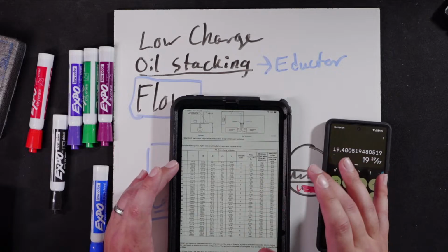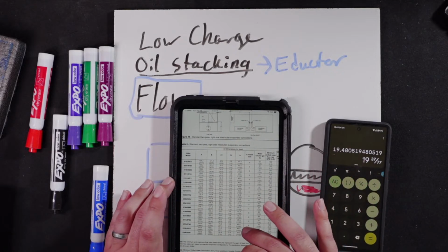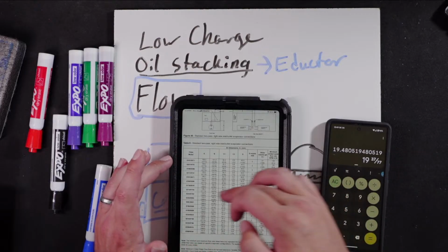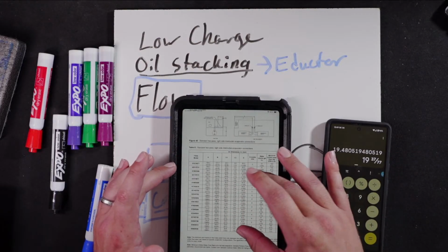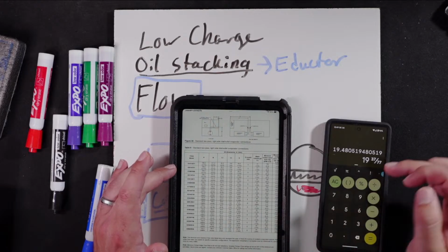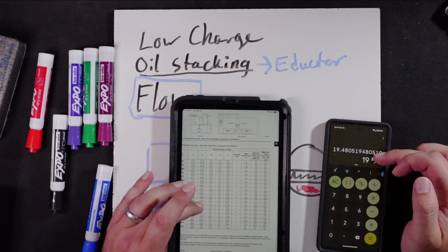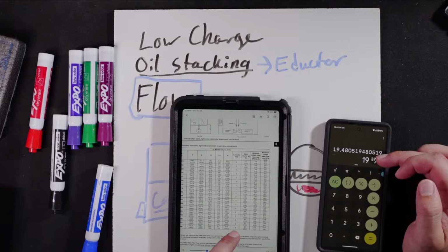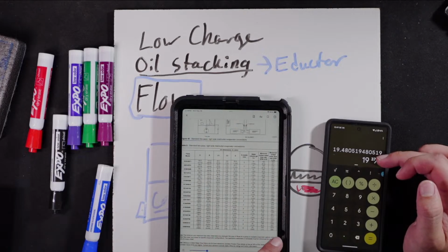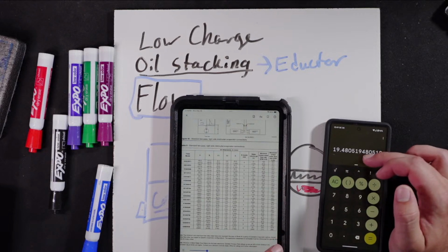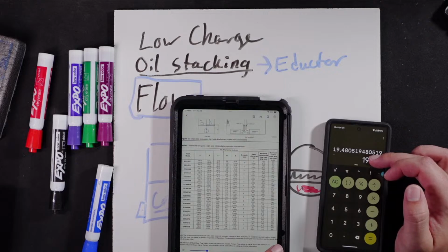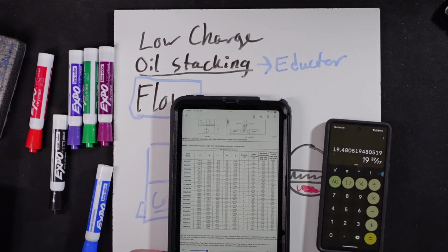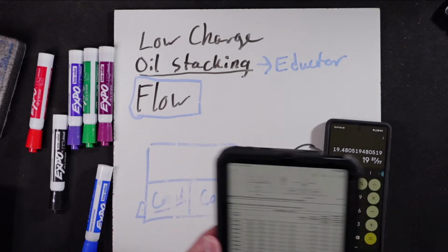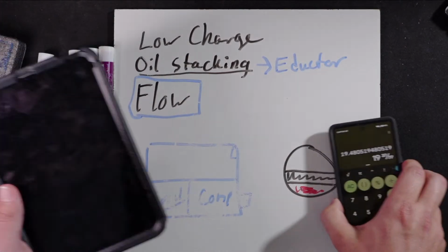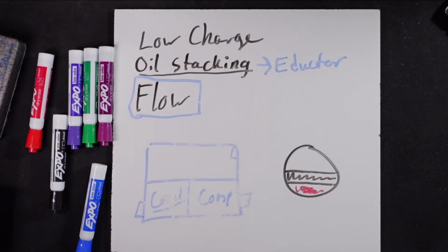Okay, well, at least we do have a way to determine this. This is the chart. If we're going to verify flow, we can base it off of this. I would say that these larger ones up here at the bottom of the chart, which can handle almost 1,600 gallons per minute, that's going to be your maximum of 19.5 PSID based off of that evaporator design. So that would be my expectation for that.